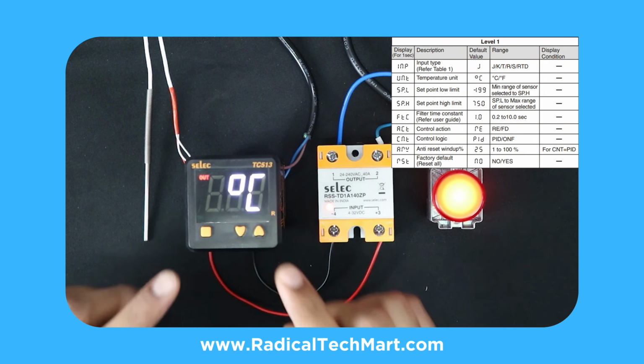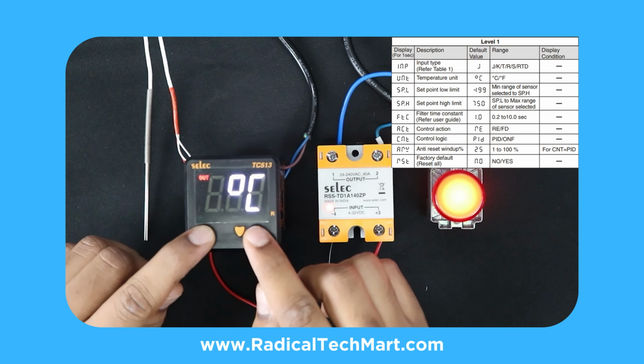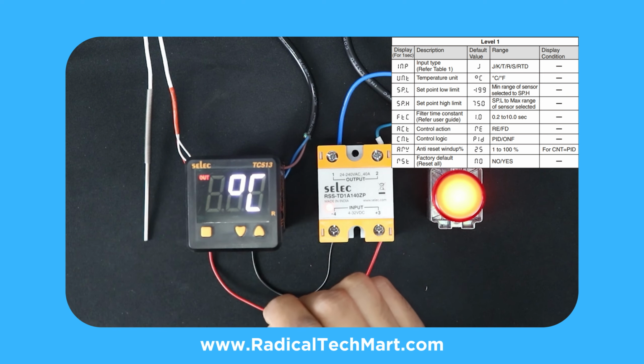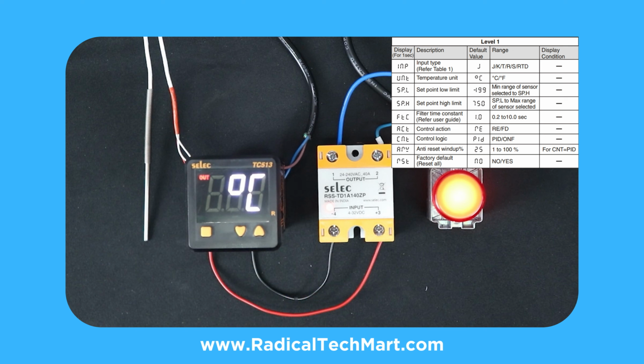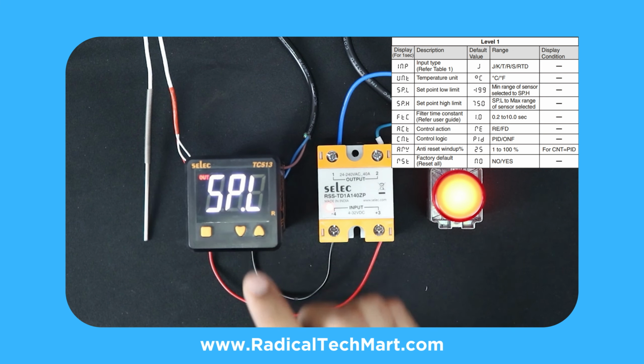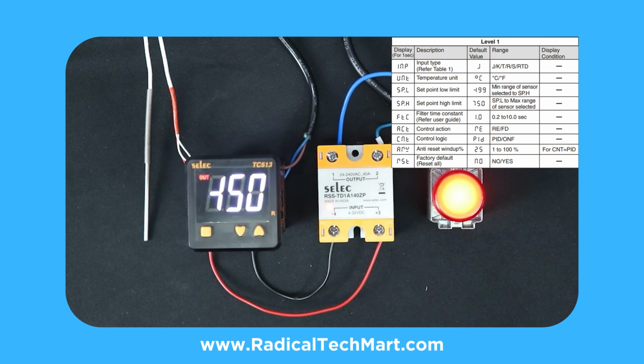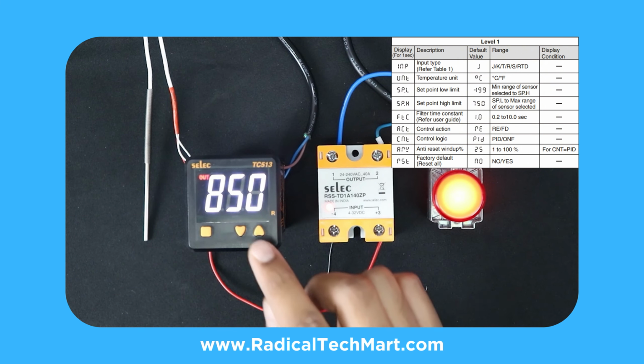Press the Instrument key to go to the next parameter, which shows the temperature unit and display. To change it to degrees Celsius or Fahrenheit, long press the Set key and Instrument key simultaneously. The next parameters are setpoint low limit and setpoint high limit. The user can set these values using these parameters.